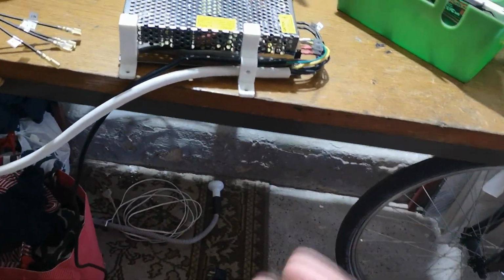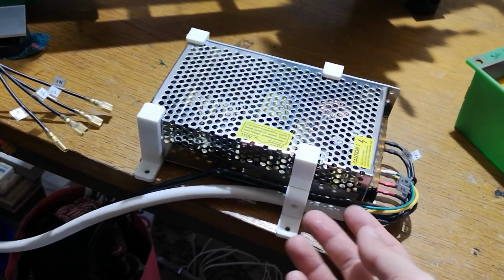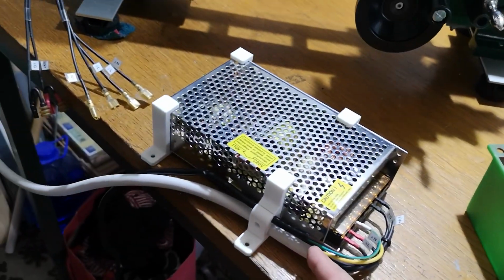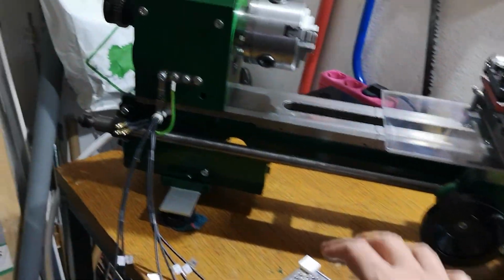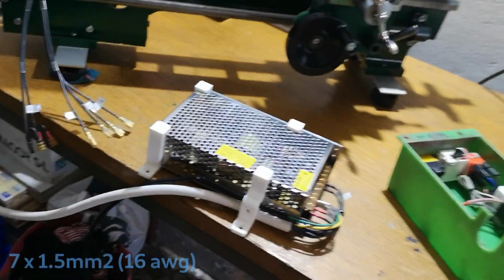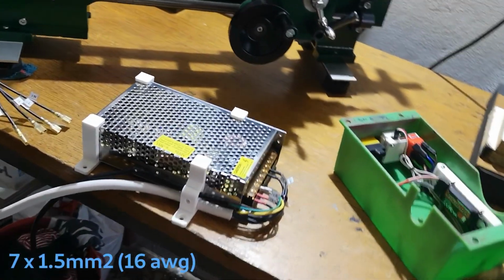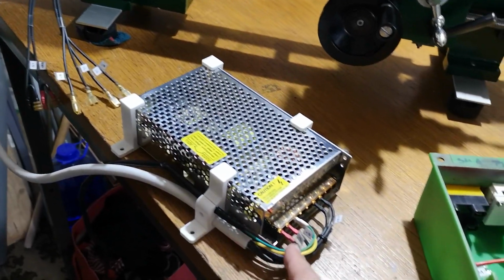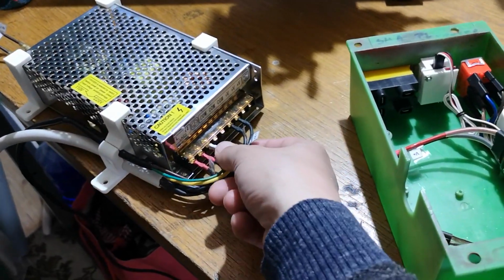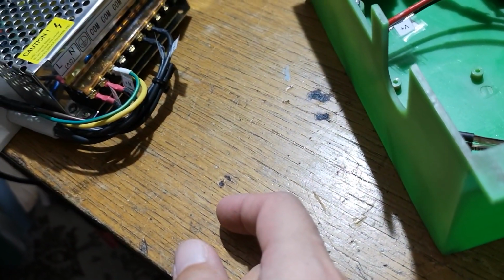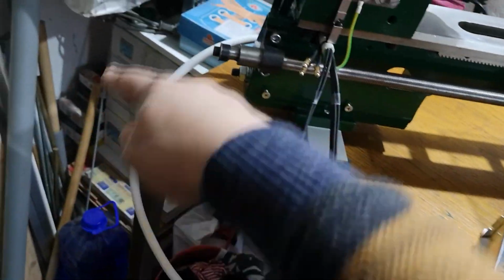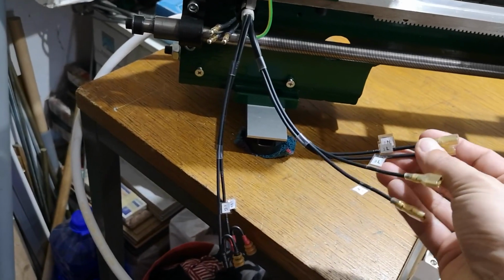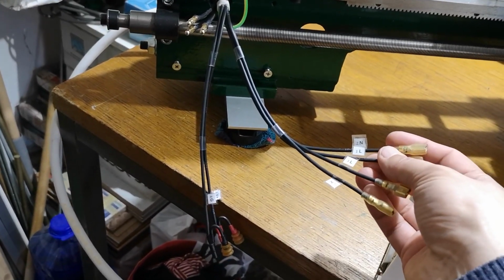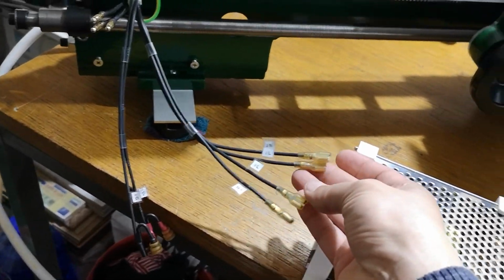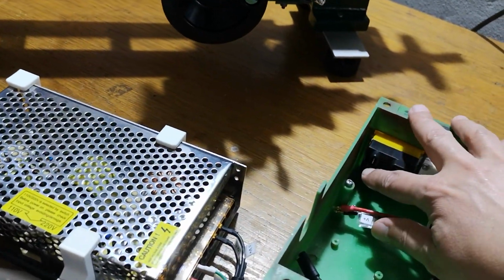Cables. The black cable is a normal power cable with three wires, and the white one that will connect the power supply and control box has seven wires, 1.5 millimeter squared each wire. So two wires from the power cable are connected to wires one and two. You can see it here, and sent through the cable, and here they are, wire one and wire two, line and neutral, and they are going to the input switch here.